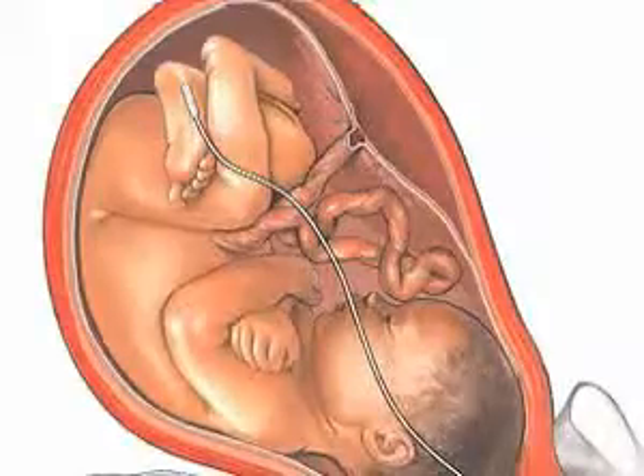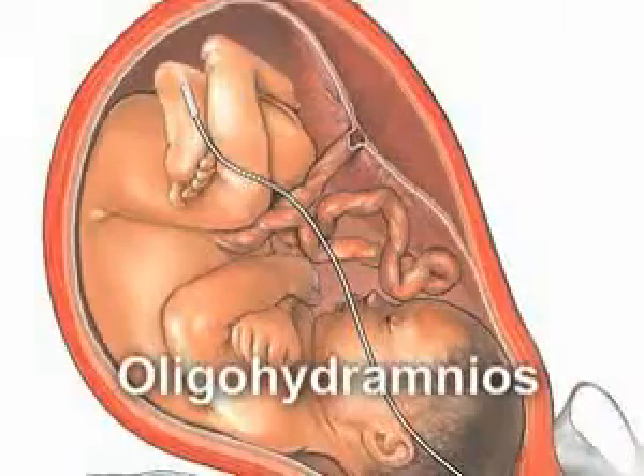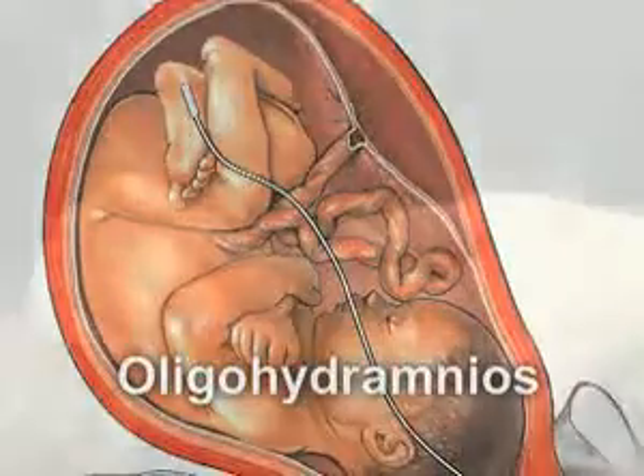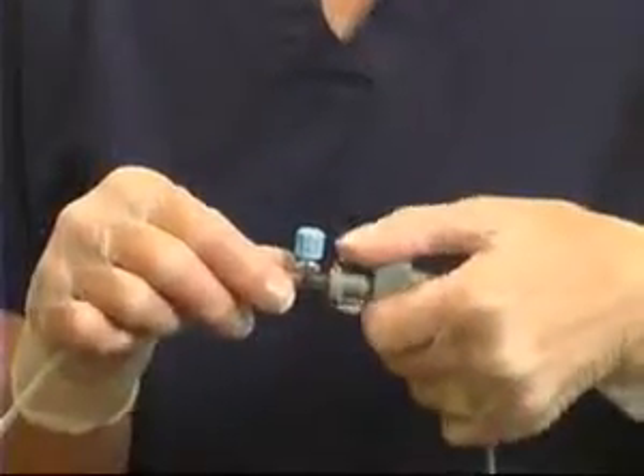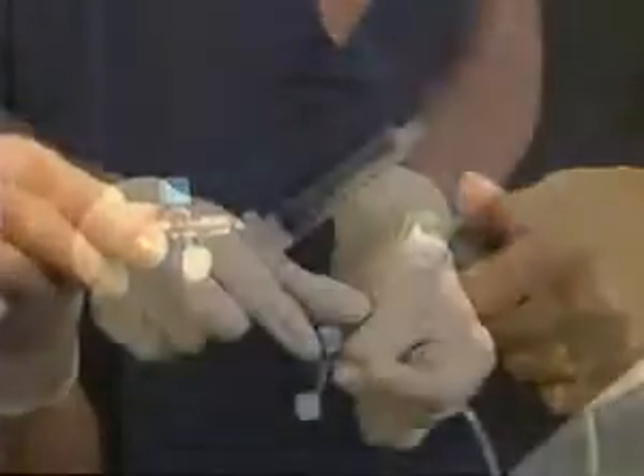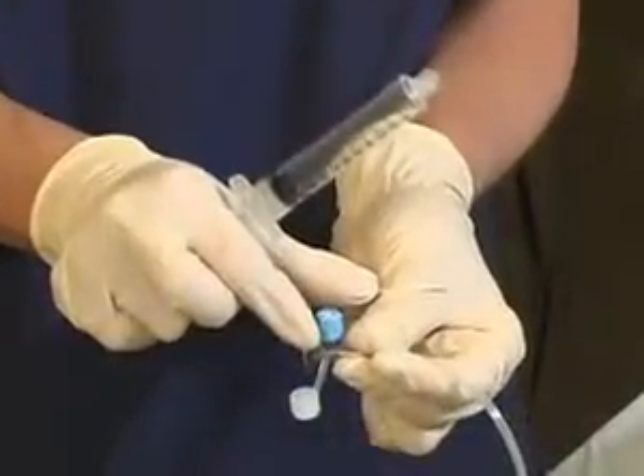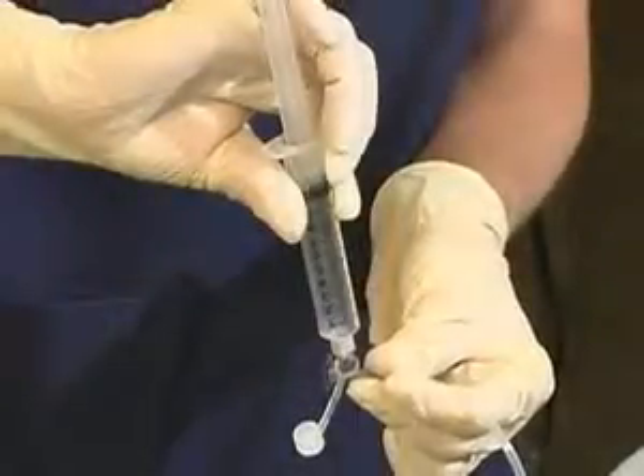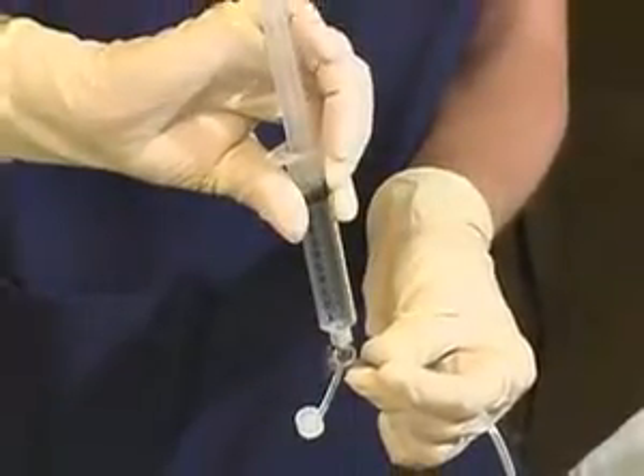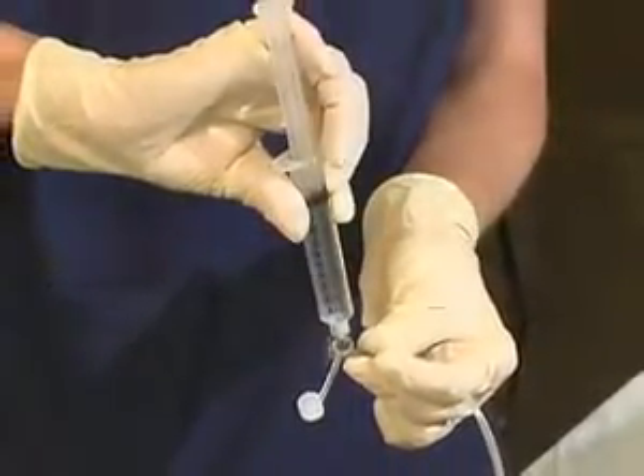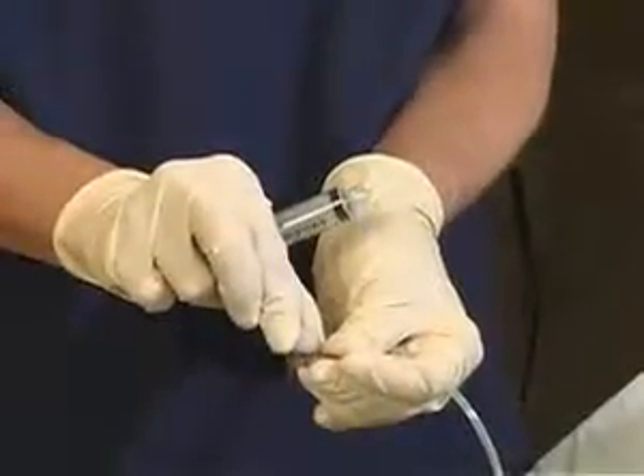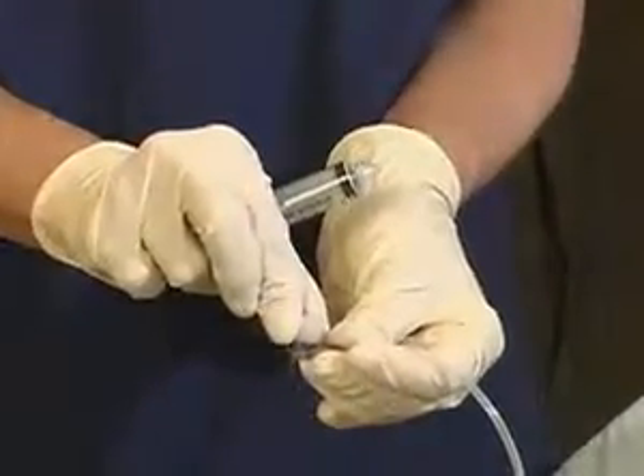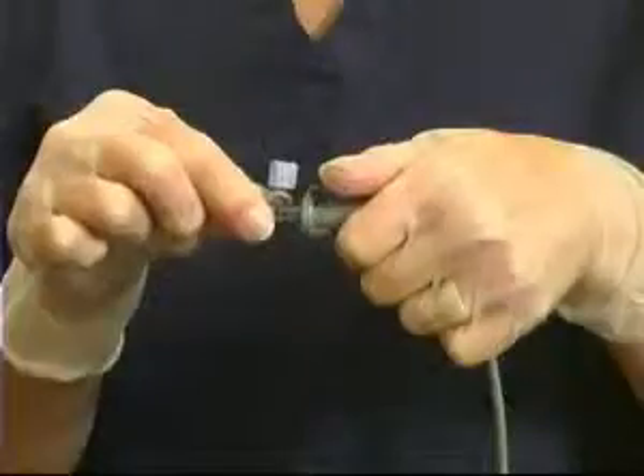If dampened waveforms are evident, but no flashback of amniotic fluid or blood is observed, oligohydramnios or dry uterus may be the cause. Disconnect the catheter from the cable. Remove the blue cap from the amnioinfusion port and gently flush the catheter with 10 to 20 cc's of sterile saline. Replace the blue cap with the tethered transparent cap and reconnect the catheter to the cable.